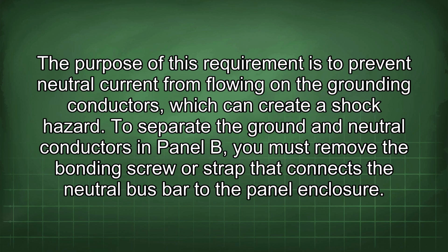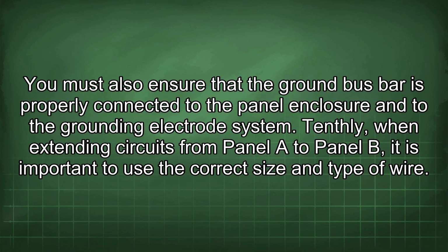To separate the ground and neutral conductors in panel B, you must remove the bonding screw or strap that connects the neutral bus bar to the panel enclosure. You must also ensure that the ground bus bar is properly connected to the panel enclosure and to the grounding electrode system.